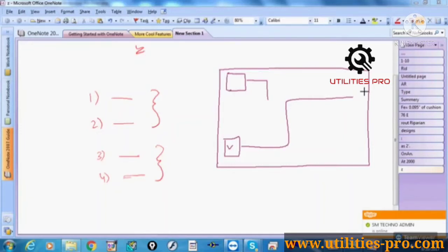Why maintenance? Because many equipments or devices are above the false ceiling or concealed, so they are not visible. If something is in the drawing but in case of maintenance the location of the equipment is different, that will create confusion for the maintenance people. So for maintenance and for the final bill, whatever changes are made on site must be updated in the shop drawing, and the modified shop drawing as per the site condition, as per the installation, we call the as-built drawing. The modified shop drawing as per the actual installation is called the as-built drawing.